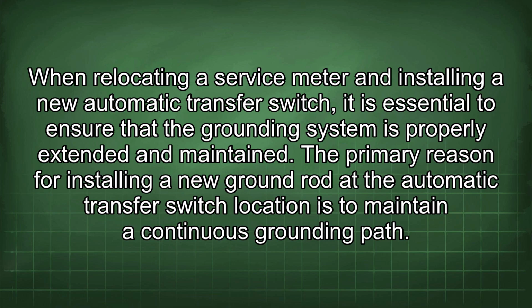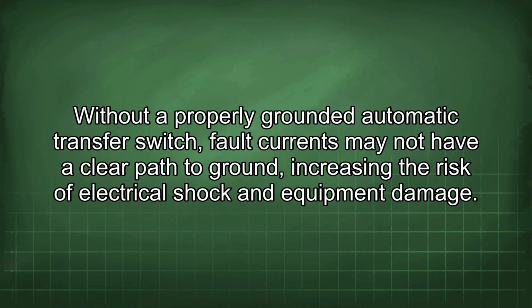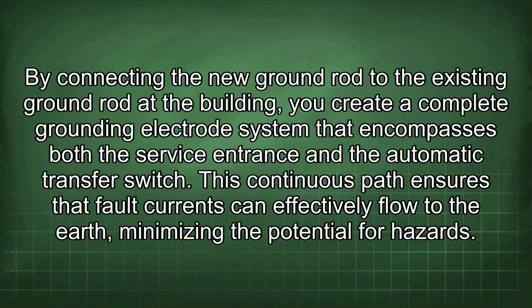The primary reason for installing a new ground rod at the automatic transfer switch location is to maintain a continuous grounding path. Without a properly grounded automatic transfer switch, fault currents may not have a clear path to ground, increasing the risk of electrical shock and equipment damage. By connecting the new ground rod to the existing ground rod at the building, you create a complete grounding electrode system that encompasses both the service entrance and the automatic transfer switch. This continuous path ensures that fault currents can effectively flow to the earth, minimizing the potential for hazards.